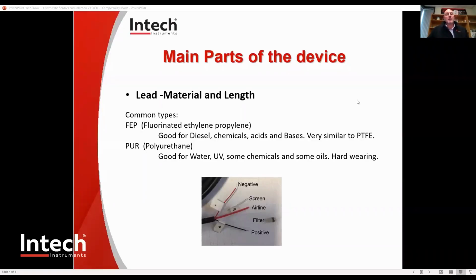So the common lead, when it comes to the lead, it's really important to consider the lead material in relation to the medium it is being submersed in, and of course the length of that lead to the depth of the hole the sensor is going to be going down. The most common material is PUR, or polyurethane. It is used in most water, grey water and sewerage applications. FEP, or fluorinated ethylene propylene, is a special material which is similar to PTFE or Teflon. It's a very hard-wearing material in most chemicals and caustic applications.